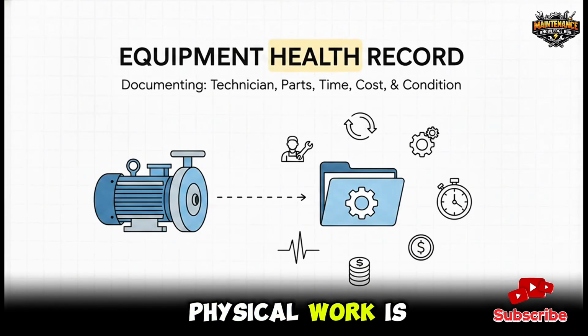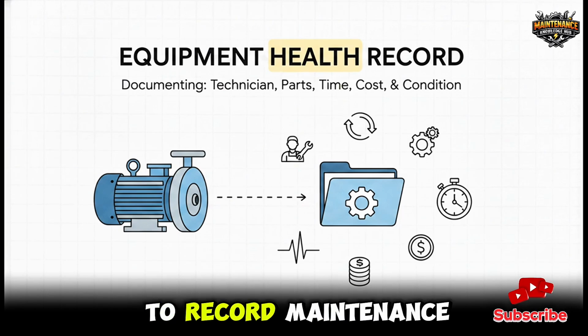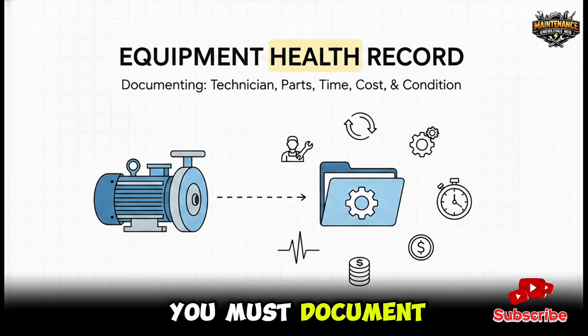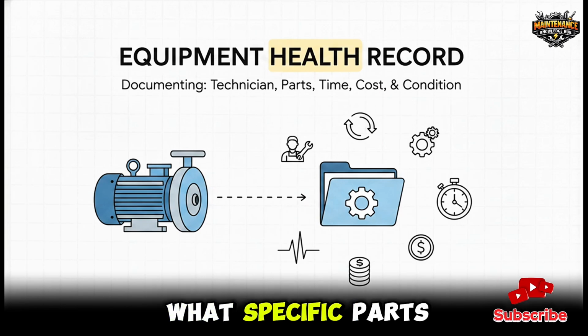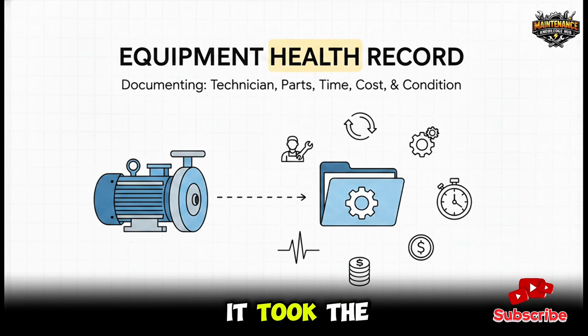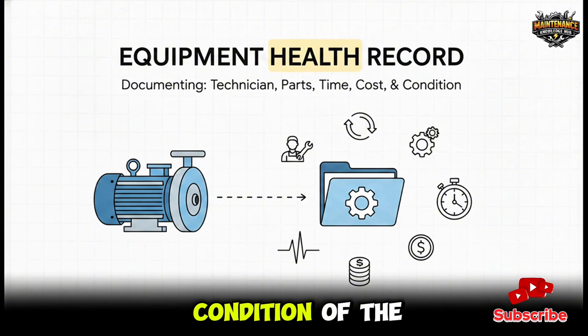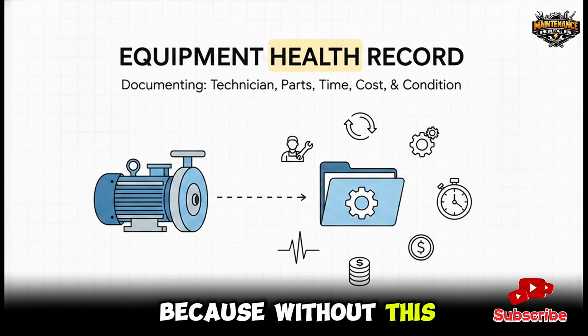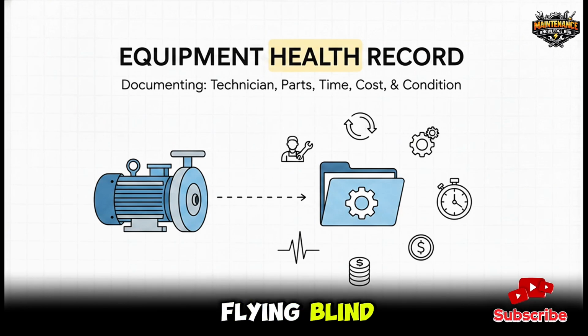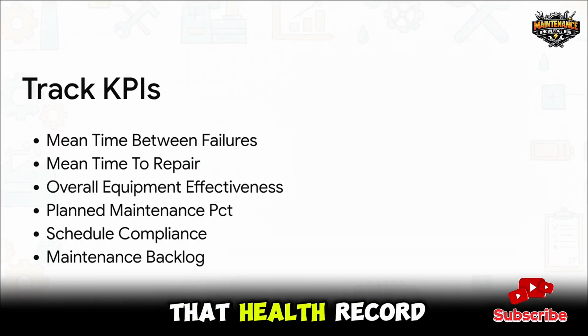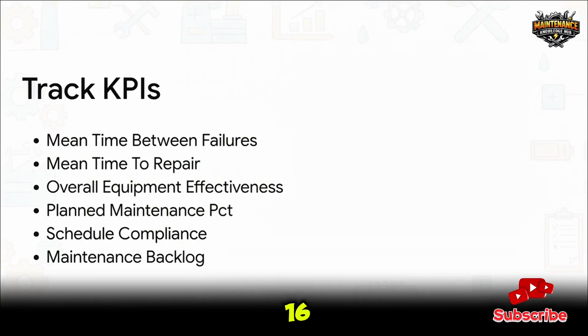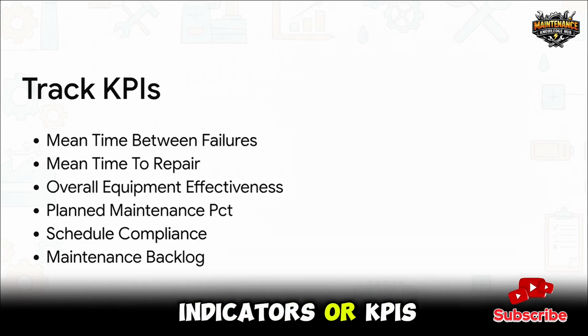Now, once the physical work is done, you can't just pack up your toolbox and walk away. Step 15 is to record maintenance history. You must document exactly who did the work, what specific parts were replaced, the exact time it took, the cost, and the overall condition of the equipment as you found it. Think of this as building a vital, ongoing health record for your entire facility. Because without this history logged, you are essentially flying blind when it comes time to plan for next month or next year. And we use that health record directly in step 16, monitor key performance indicators, or KPIs.